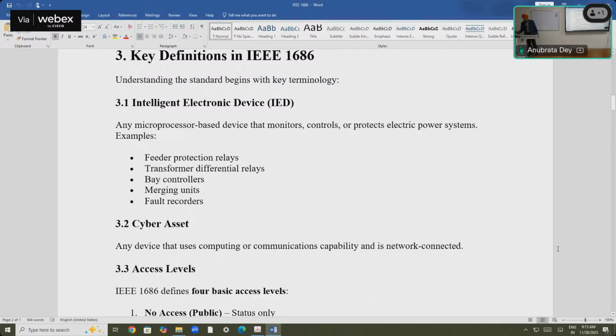What is included in this standard? All IEDs - any microprocessor-based device that monitors, controls, and protects the electric power system falls within that category, including fault recorders and merging units. Sometimes we think IED just means the protection relay, but intelligent electronic device includes bay controllers, transformer differential relays, feeder protection relays - all types of protection relays along with merging units, fault recorders, or bay controllers.